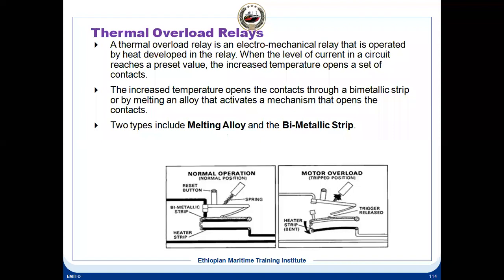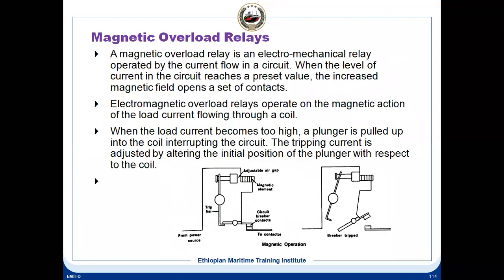Yes, overload means it is heating. Suppose the pump bearing gets stuck, what will happen in this case? The motor becomes a locked rotor. The locked rotor current will increase, so the current will increase. So it's a heating effect. Because of this current increase, the heating, in a thermal overload this bimetallic strip will open.